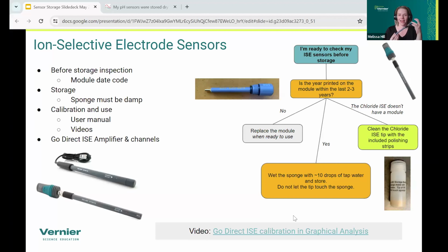Oh, you know why I can't unscrew it? Because it's a chloride ion selective electrode. Chloride does not have a module. So if your chloride ISE is giving you some weird data, you just take a polishing strip and rub the edge of it till the data looks better. So when you unscrew the tip, if there was a module here, I would just unscrew this. And then it looks like this picture right here on the slide deck.